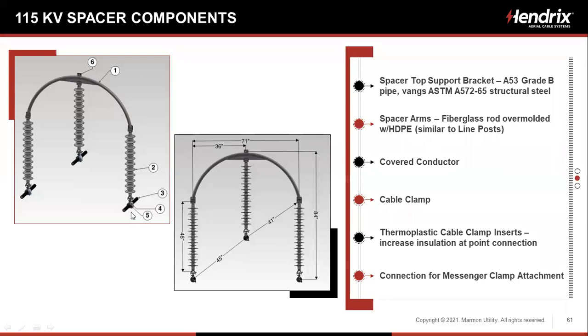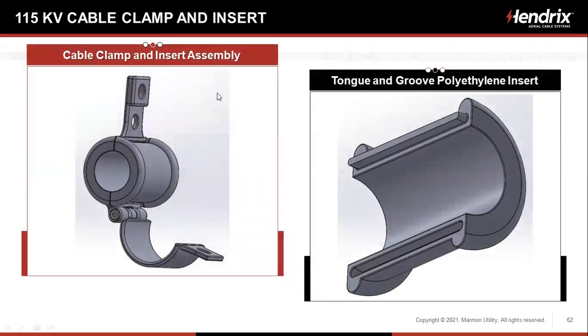The covered conductor there in the clamp, we have the cable clamp. We have thermoplastic cable inserts. It's going to increase the insulation around the cable at the point of connection to that spacer. And then we have the messenger attachment. Let's take a look a little closer.